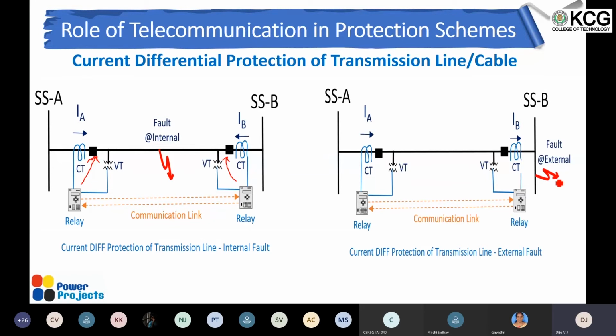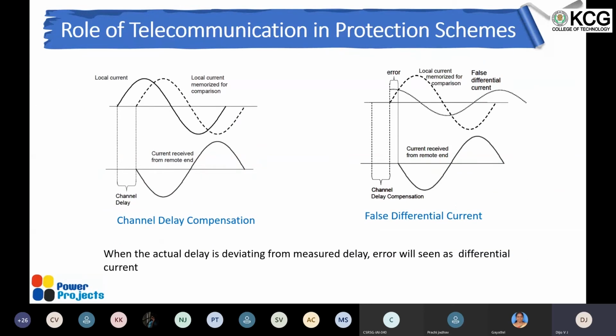So here someone can have a doubt. In the previous case, both connections were coming directly to the relay, right? But now it is going to different relays, and there is a communication between these two. This communication might create a delay in the reception of current and voltage information at the other end. So that can create an issue, isn't it? The instantaneous values used for comparison may not be exactly at the same instant, because there is a communication propagation delay. This is the issue we were talking about.